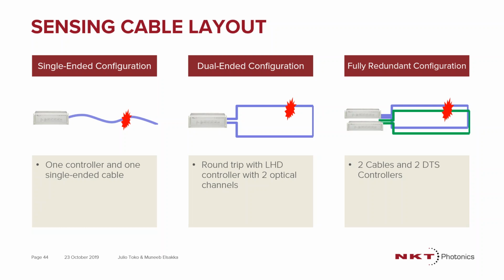You can have one controller and one single-ended cable setup, and that would not include you coming back to the controller, but you still will be able to sense up to the end of the cable, and this will give you the maximum coverage as part of the approval for the controller. You can also cut this distance in half and do more of a looped approach, which is definitely more recommended. In the event that you have a fiber break, you can always detect all the points along the cable before the break and then after the break.